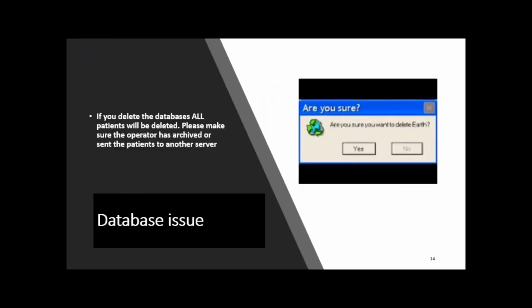All right. Now, if the computer boots up all the way, but the operator can't scan, check the databases. When databases get full, the computer's going to have issues. And the problem here is there's more than one way to delete patients. So the operator could be deleting them wrong and not even know it. So if I have any doubts, I'm going to delete the databases and start fresh. But one thing is let the operators know and remind them that when you delete the databases, it's all going to be gone. There's going to be nothing left and you can't get it back. And I've done that when the operator said, okay, and then they ran back in and said, did you do it? Yeah, that's a real rough time because you can't get them back and they have to rescan.